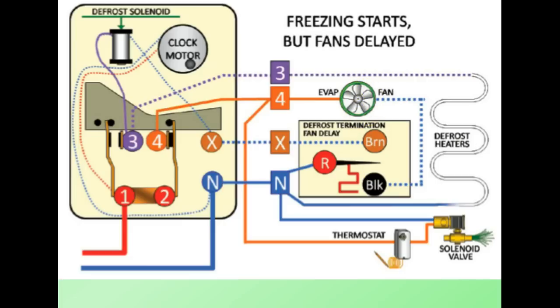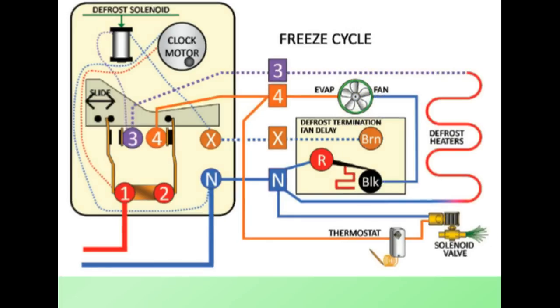We're back to the freeze cycle now. After the coil has cooled down to 25 degrees Fahrenheit, the fan delay part of the defrost termination and fan delay has now made contact to allow the neutral to flow through to turn on the fans. So we're back to where we originally started.